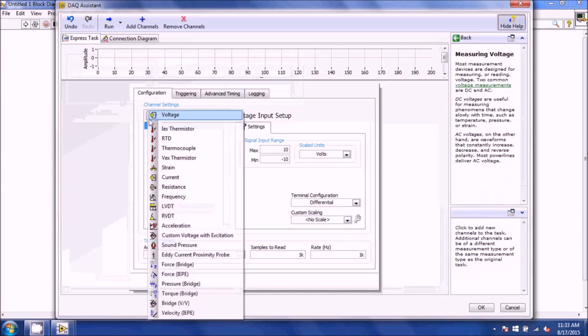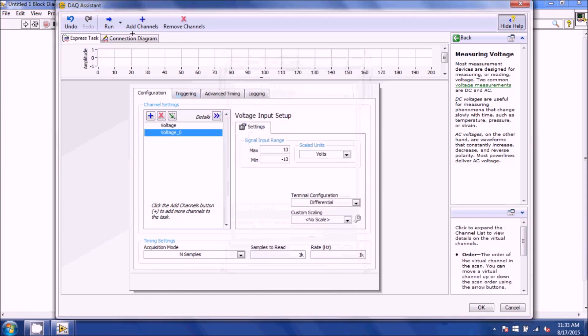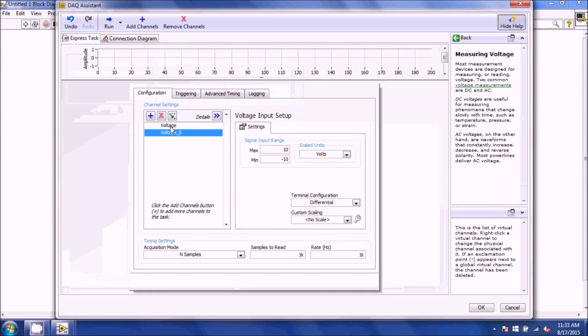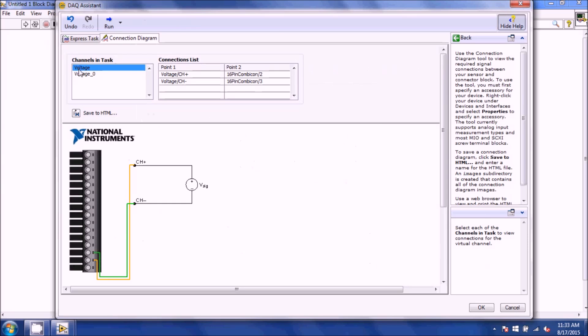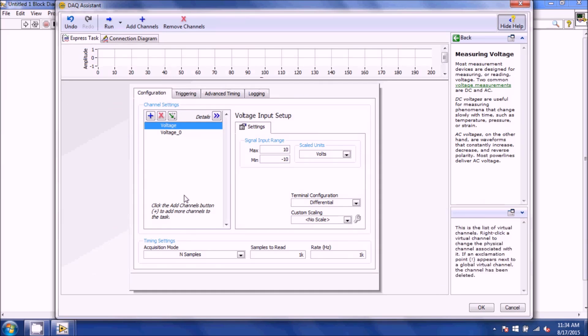If you add in another signal, say AI3, and go to Connection Diagrams, it will show you the wiring for that signal. You can select the voltage signal individually to view its connection. You can also save this to an HTML file. I'll post the pinouts of the DAQ itself as well as the manual. Remember, you can only use those certain input-scaled ranges, and your DAQ resolution changes based on the scale input you select.